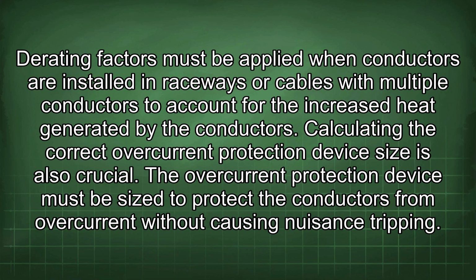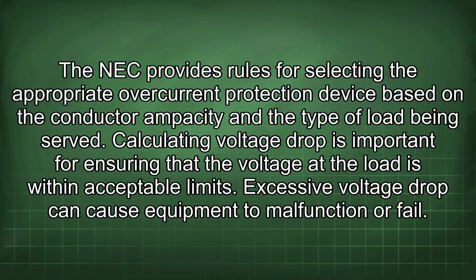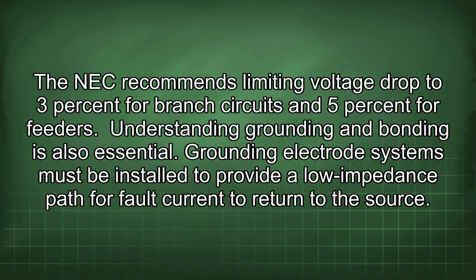Calculating the correct overcurrent protection device size is also crucial. The overcurrent protection device must be sized to protect the conductors from overcurrent without causing nuisance tripping. The NEC provides rules for selecting the appropriate overcurrent protection device based on the conductor ampacity and the type of load being served. Calculating voltage drop is important for ensuring that the voltage at the load is within acceptable limits. Excessive voltage drop can cause equipment to malfunction or fail. The NEC recommends limiting voltage drop to 3% for branch circuits and 5% for feeders.